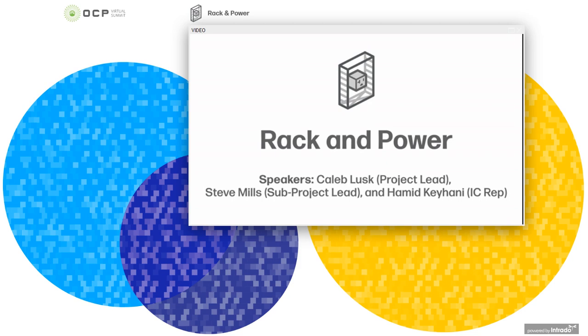So we have defined the interfaces between the bus bar and the rack. Rittal submitted those, was it last year, Caleb? It's been at least a year. Yeah, at least a year. So there's a specification out on the Rack and Power wiki, as well as in the contributions database on the OCP website, that defines all the interfaces between the bus bar and the rack.